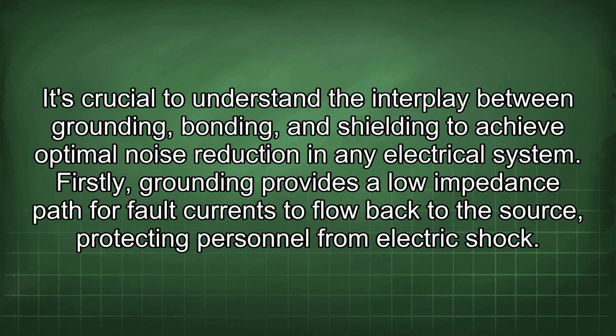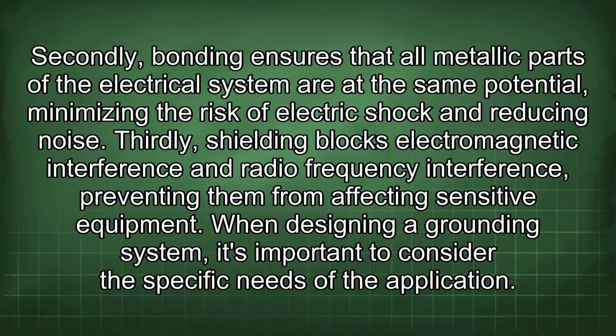Firstly, grounding provides a low impedance path for fault currents to flow back to the source, protecting personnel from electric shock. Secondly, bonding ensures that all metallic parts of the electrical system are at the same potential, minimizing the risk of electric shock and reducing noise. Thirdly, shielding blocks electromagnetic interference and radio frequency interference, preventing them from affecting sensitive equipment.